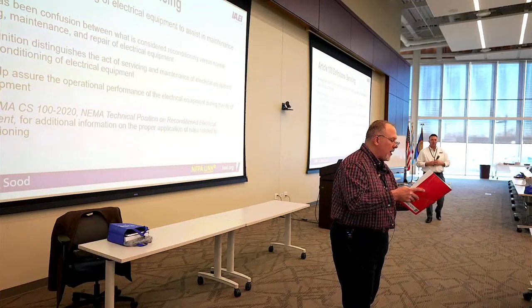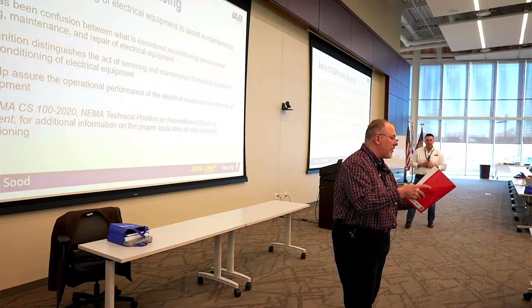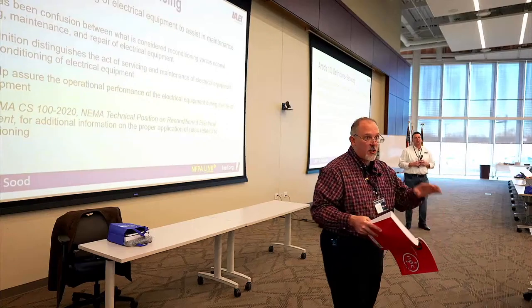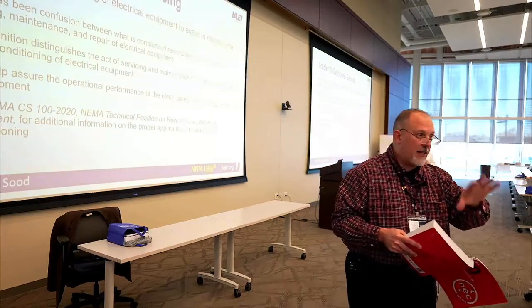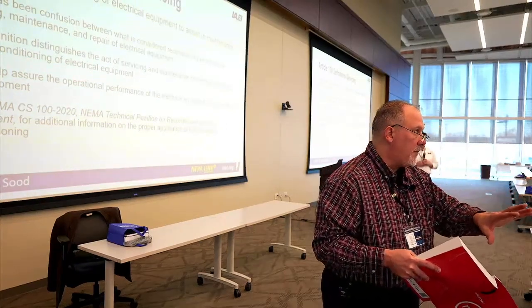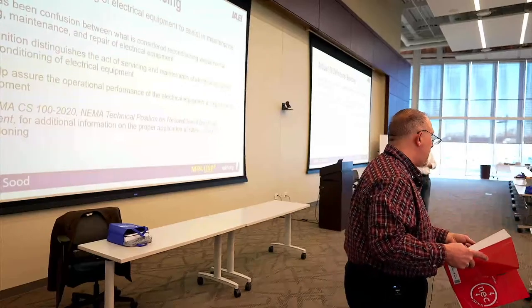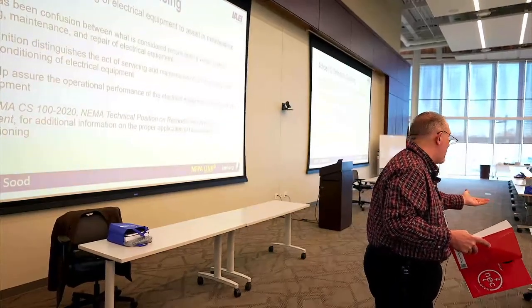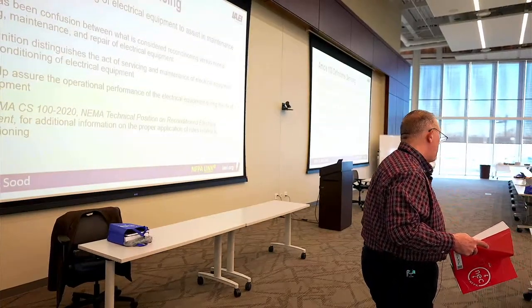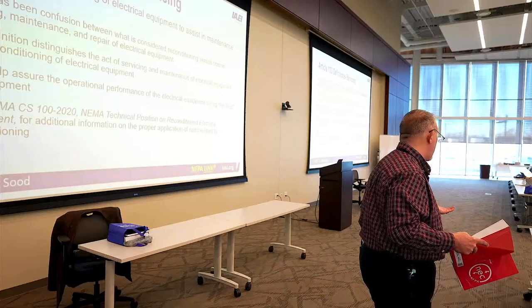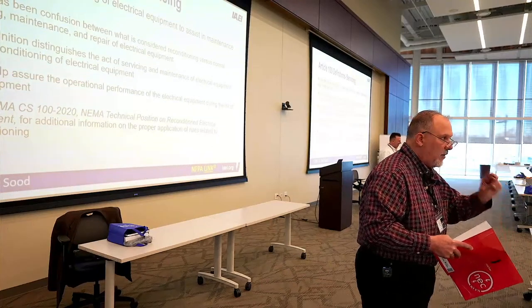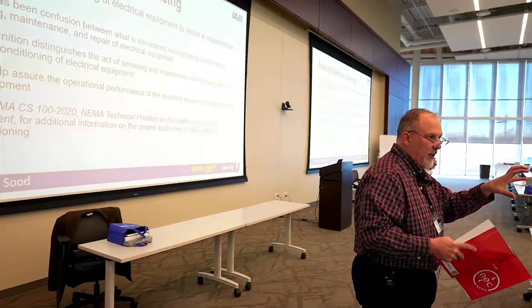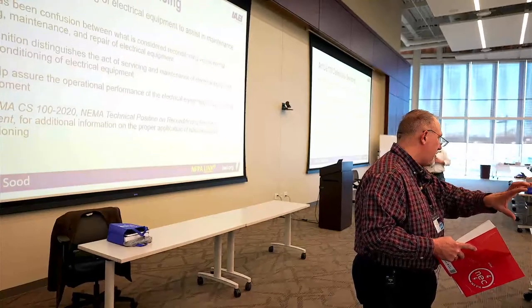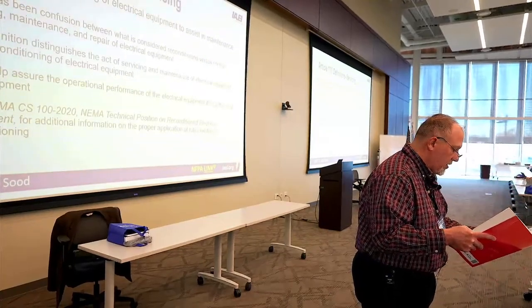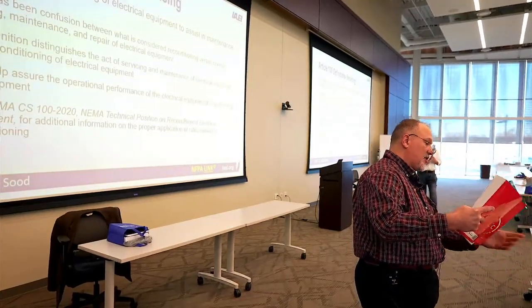Equipment that is restored to operating condition shall be reconditioned with identified replacement parts. So any parts you put in there have to be identified. By who? It could be identified by the manufacturer. But what if it's a 1942 breaker and the manufacturer is maybe six foot under? I don't know where that company is. You can still follow anybody who makes those parts, and follow their instructions on how to properly install those parts because there are conditions here.